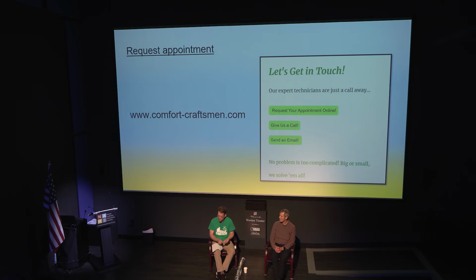In the summertime when it's too humid, refrigerant-based systems have trouble removing that humidity. They don't remove it as well as a water-based or hydronic system. So there's a way to have a hydronic air handler. Because of the way things work, you're able to pull more moisture out of your home's air by using hydronic equipment in your ductwork. That's the hidden secret around hydronic cooling—it can take more humidity out than a refrigerant-based system.